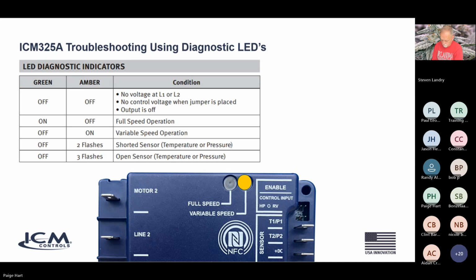If it doesn't do that, if something is wrong, then it's going to flash you a code. So if both of these lights are off, it means you have no voltage at line 1 or line 2. If both of those lights are off, it also could mean you have no control voltage when you have the control voltage input selected. Or it means that simply the output is off. It's just not ready to turn on yet because your pressure in your system is too low.